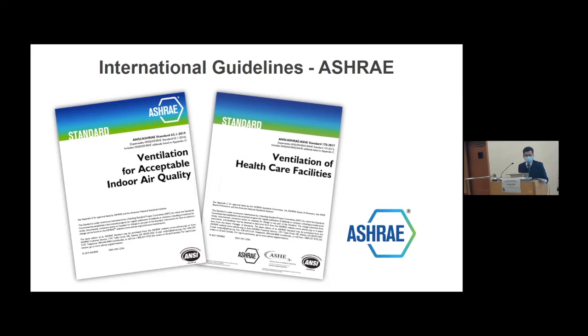This is a standard that addresses procedures for testing indoor air quality and for measuring ventilation rates for mechanical and natural ventilation. The second standard is ASHRAE 170 on ventilation of healthcare facilities, with its latest version issued in 2017. This is a standard often referred to by engineering consultants on the design of hospitals and clinics in Hong Kong. It states the different ventilation requirements for commonly found occupational areas at healthcare facilities. For different types of isolation wards at hospitals, it has its particular set of requirements.